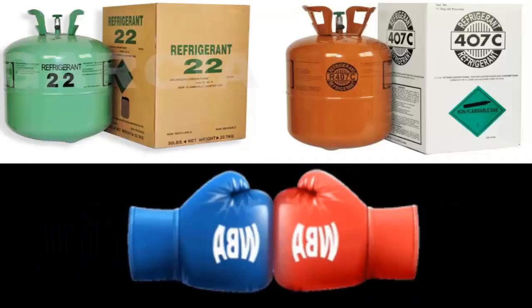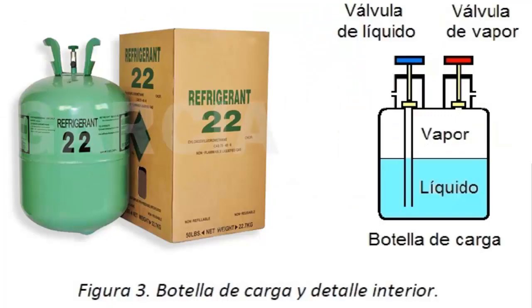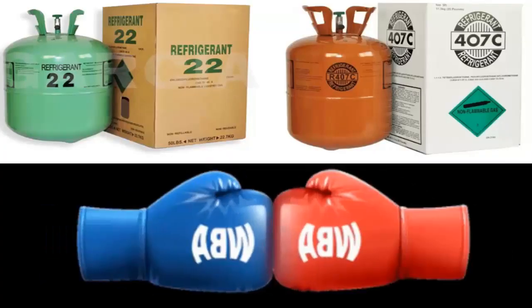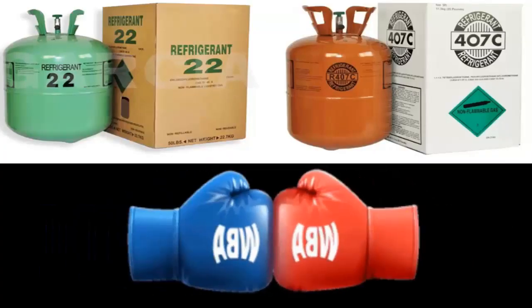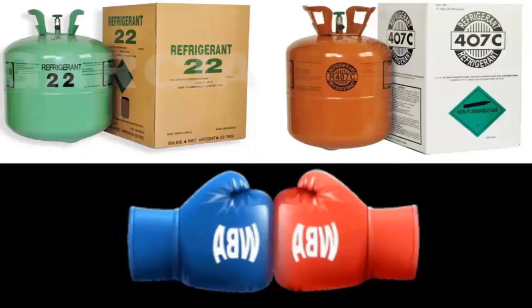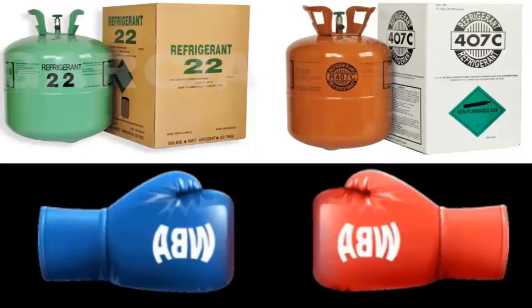In the case of R-22, it is possible to recharge it in both liquid and gaseous phases without any issues. This is due to its nature as a pure refrigerant. However, R-407C, being a gas mixture, must always be recharged in the liquid phase. This is an important consideration to keep in mind when performing maintenance on refrigeration systems.